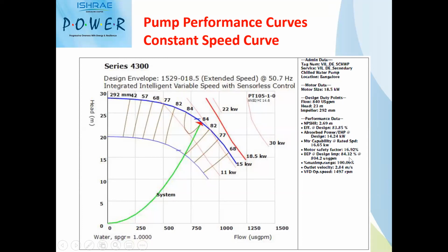We have a cushion of 16.92% for power. Your absorbed power is 14.24. My motor sizing is 18.5. The cushion, which is called the motor safety factor, is 16.92. And what is the BEP? BEP point is somewhere around 84.12%.